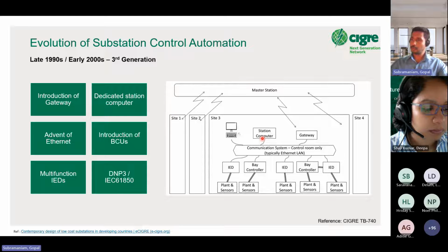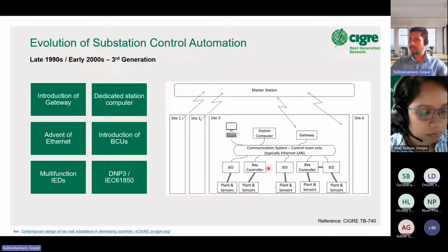And this period also saw the implementation of a separate bay control unit. The modern relays here were mostly multifunction relays, quite similar to the digital IEDs which we see in recent days. And there was an overload of functions and various data points, due to which there was a need for a separate bay controller, which took over the interlocks and various control functionalities. And there is no clear distinction between the third generation and fourth generation, and so this may generally cover even DNP3 and 61850 protocol.